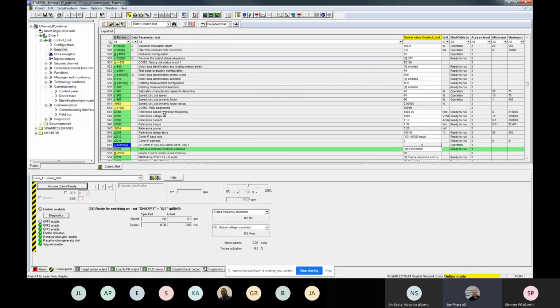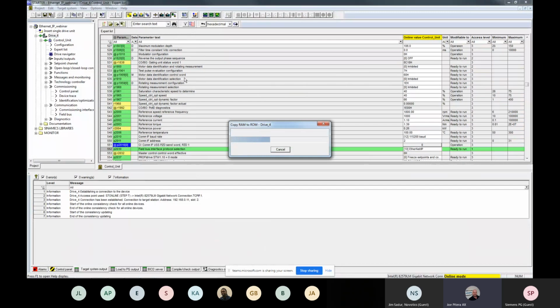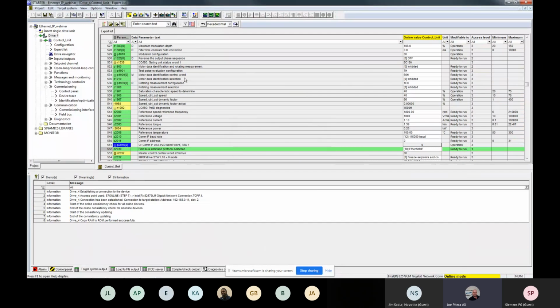So we are going to copy RAM to ROM onto the drive unit, copy RAM to ROM. I'm going to save the project. And there is a trick here, so I'm going to teach you this trick. By going to parameter 972, you could do a drive unit reset, which is really a reboot without cycling the power. So we're going to go to a hardware reset immediate here, and this is a software reboot for the system.